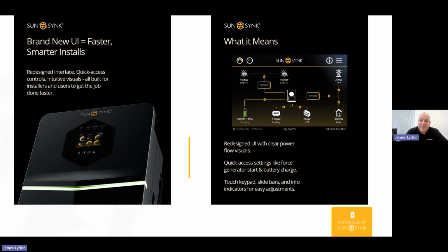We've added some quick access settings like force generator. So on the previous UI with the backup generator integration, you would have to go into the timers and set when you want it to come on. With the new UI, you can quite simply go in and force charge the batteries from the generator, and you can also force charge the batteries from the grid. Full touchscreen display. We've got full slide bars for the control, and yeah, it's nice and sleek.